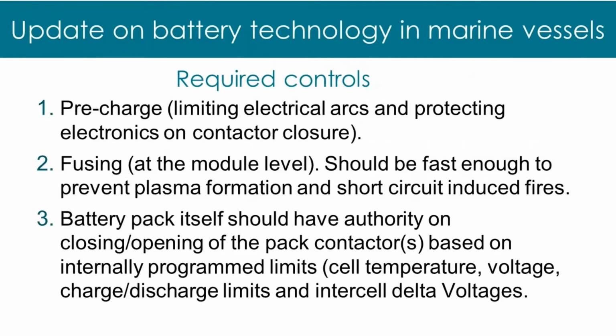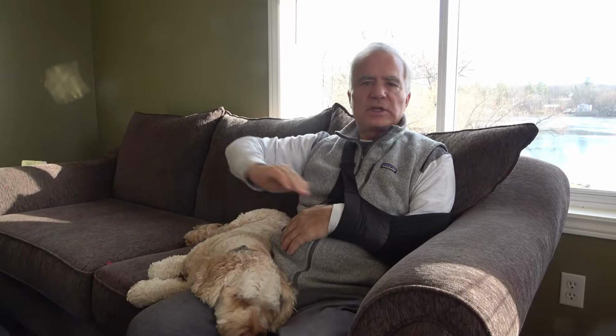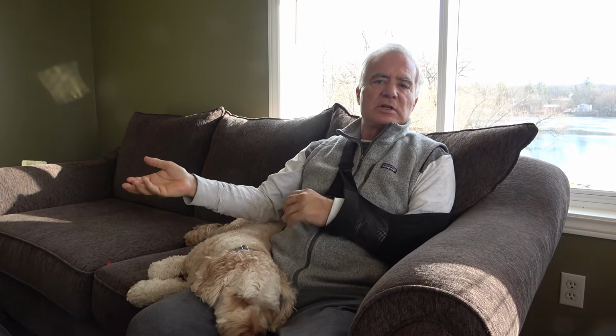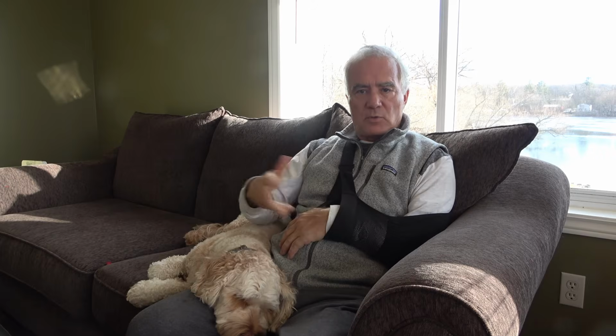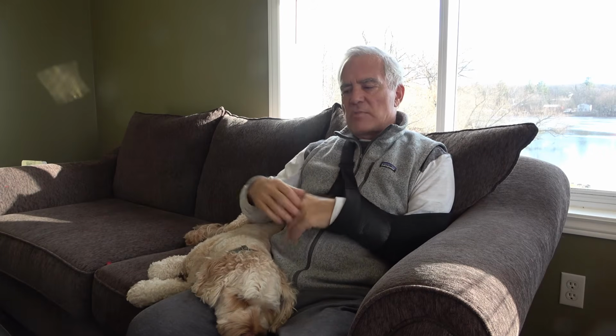Very often, if the batteries are well protected and well controlled, meaning you know the voltage of every cell and the temperature is monitored, then having just one fuse at the end is acceptable. If you're in parallel, then, as I said, parallel and series fusing is required also. But that's for the fusing level. Then when you close a contactor on a battery, you're actually creating a big voltage spike. I mean, your boat is dead, and all of a sudden it has 12, 24, or 48 volts, depending on what voltage you're using. So that voltage inrush current comes all at the same time.